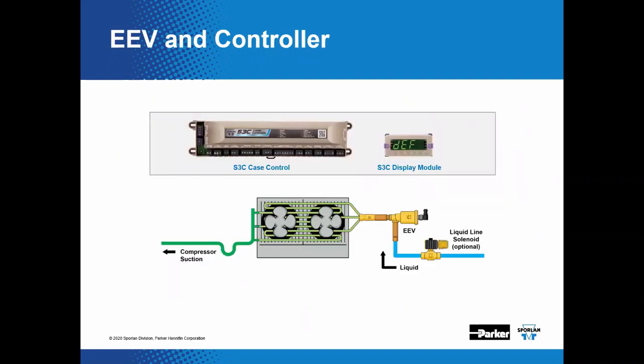The S3C case controller is capable of controlling and monitoring single temperature, single evaporator, self-contained refrigerated fixtures. In this example, one controller can do the job since we are only using a single EEV, as we see right here. When we include additional electrically actuated, electronically controlled valves, that valve module might become necessary. In fact, it's an extension of the case controller, and it'll make things like that possible. The controller will also control all typical case functions and receive the desired sensor inputs and drive the EEV. This control method would allow the EEV to regulate superheat. The controller would also drive the so-called optional liquid line solenoid valve to successively open and closed positions and open and close the EEV to control case temperature.